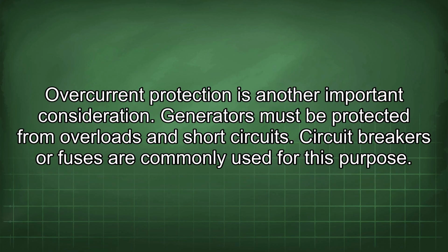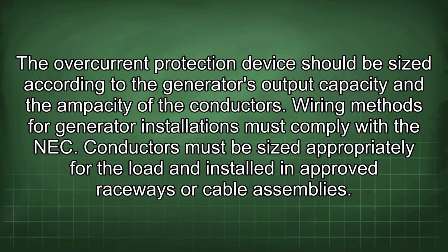Overcurrent protection is another important consideration. Generators must be protected from overloads and short circuits. Circuit breakers or fuses are commonly used for this purpose. The overcurrent protection device should be sized according to the generator's output capacity and the ampacity of the conductors.